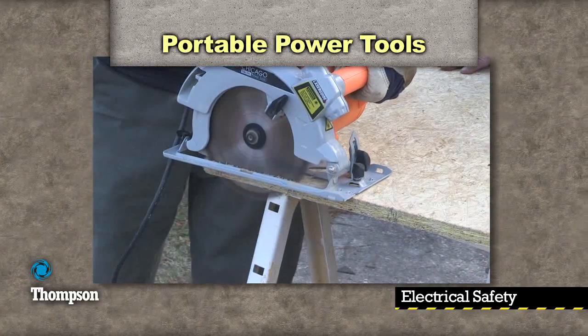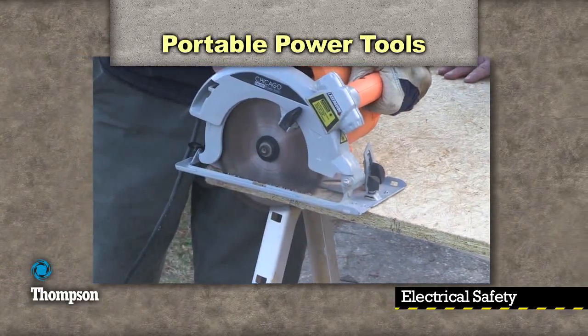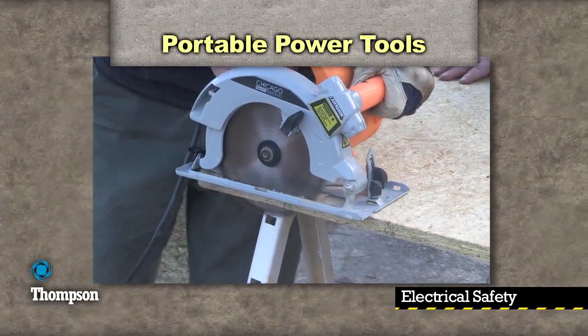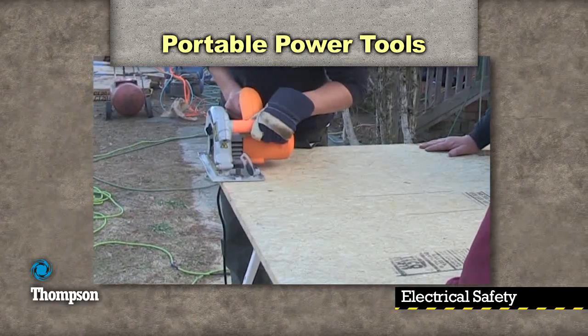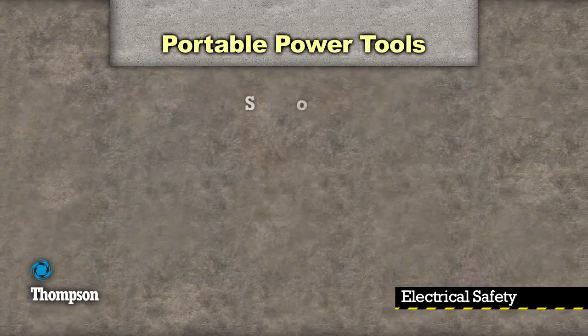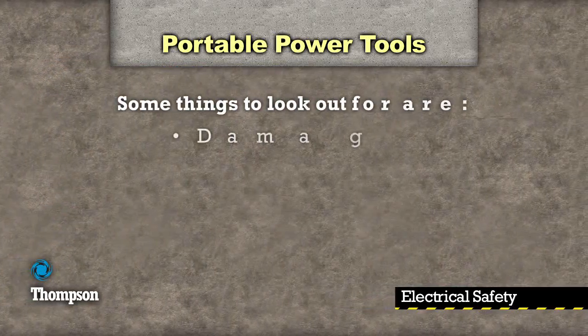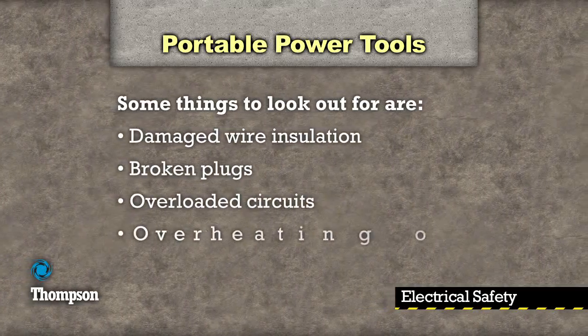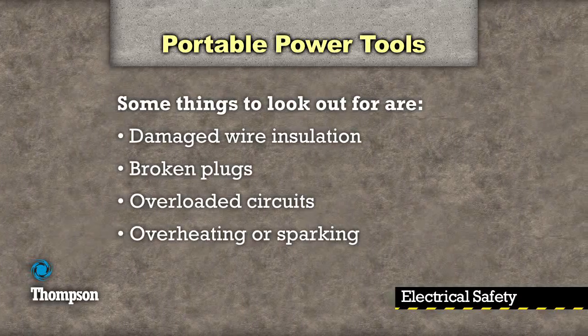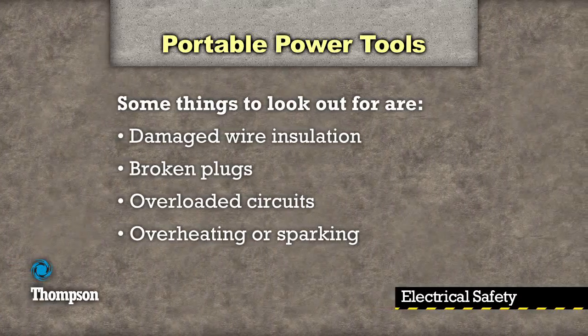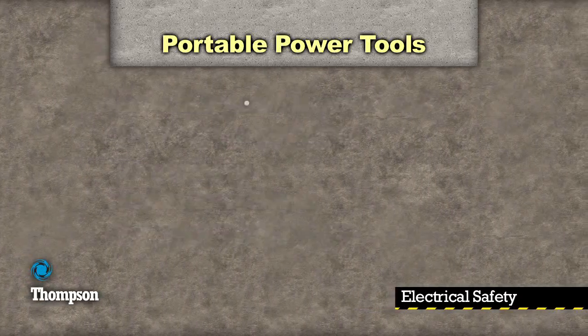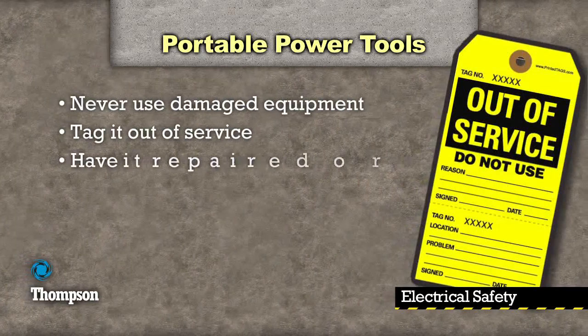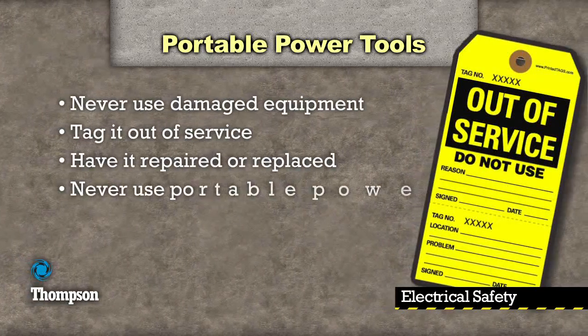Portable power tools are used by almost everyone, either at work or at home. They require proper care and inspection to reduce the risk of electrical danger. Some things to look out for are damaged wire insulation, broken plugs, overloaded circuits such as a device that pops a fuse when turned on, overheating or sparking. If you find a power tool that is damaged, tag it out of service and place it in your supervisor's possession so that it can be repaired or replaced.